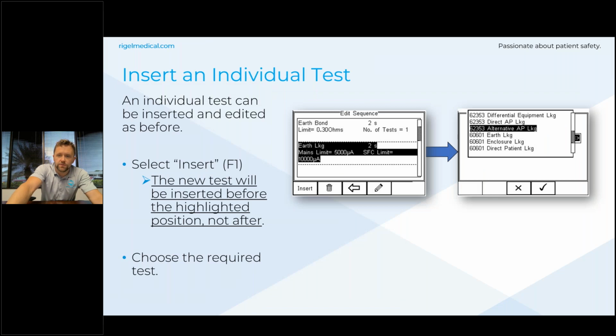You can insert individual tests in between of those test sequences. So if you wanted to add an additional earth bond test or an IEC lead test, then you can input that into the sequence as well as changing the limits to it.